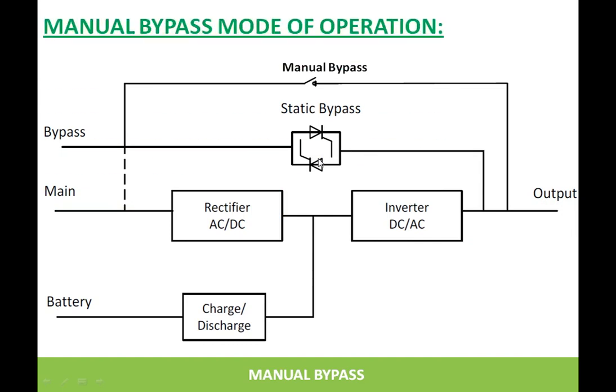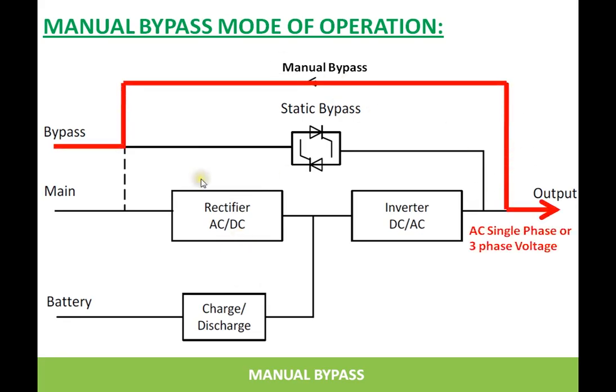The other mode is manual bypass mode, and the UPS is put into this mode whenever maintenance needs to be carried out on the UPS system. The maintenance person can perform the required maintenance without disturbing the load. During the maintenance operation, output is available through the manual bypass. It is just an MCB — when switched on, whatever mains voltage is present is fed directly through the bypass switch to the output. In this mode there is no voltage regulation; the same incoming mains voltage is fed to the output.